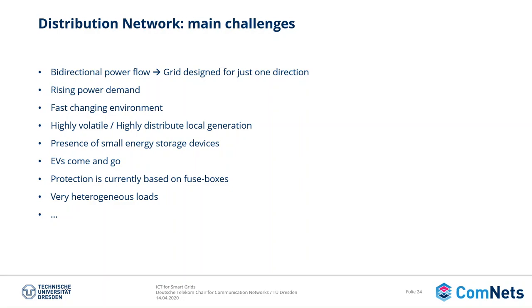One of the biggest challenges, in my opinion, is protection right now. The protection side of the distribution network is based on fuse boxes. The way these fuse boxes work is like any other fuse box: it measures the current passing in one direction, and if this current is higher than a certain threshold for a certain amount of time, then the fuse drops and you are isolated from the grid.